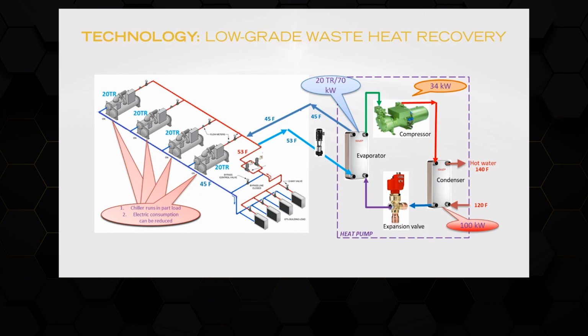In a compressor, as we know, the refrigerant is compressed, thereby increasing its pressure and temperature. This high-temperature refrigerant then passes through another heat exchanger called a condenser, where it releases that heat, and that heat is picked up by hot water return coming from the facility. So by installing a heat pump, we can raise the low-grade waste heat to medium-grade usable heat, which can then be used for process heating.